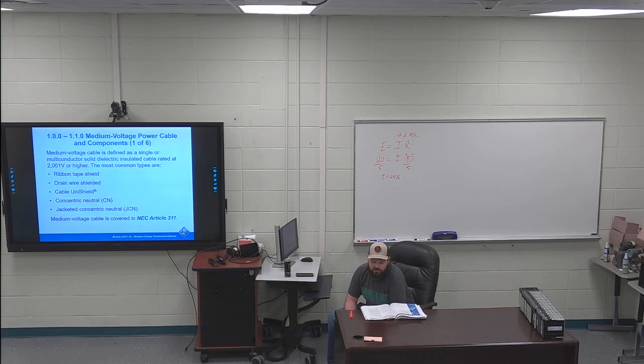111, medium voltage cable configuration components. So they can have different types of wire inside of a cable. You can have concentric stranding, compressed stranding, compact stranding, solid wire. I have the third bullet point, the compact stranding, highlighted. Compacted to 90% of the concentric conductor diameters.